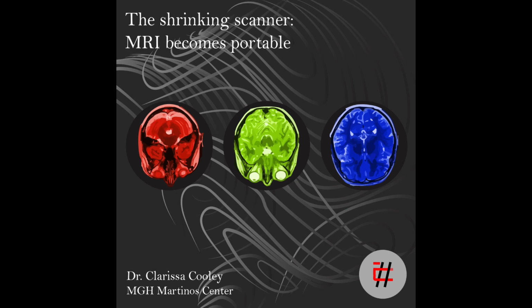You already mentioned conventional MRI scanners try to have a highly homogeneous magnetic field. So how does this differ in the portable system? Yeah, so that's one of the main things about our scanner that's different from other scanners. We decided to relax this constraint on the homogeneity of the magnet to allow us to design a much more compact magnet. It's really hard to create a really homogeneous field with a small magnet.